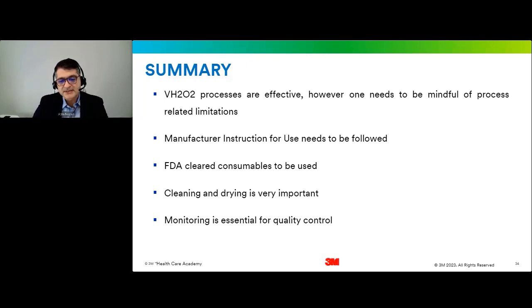And monitoring is essential for quality control, and we talked about that. We have physical monitors, the printouts, either a paper printout or a digital copy from your sterilizer, which show whether the cycle parameters they were designed for have been met. It's very important. Chemical indicators have their own role, either as external or internal chemical indicators, and there are biological indicators and the PCDs for monitoring the efficacy of the process.